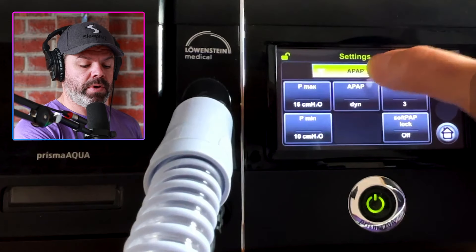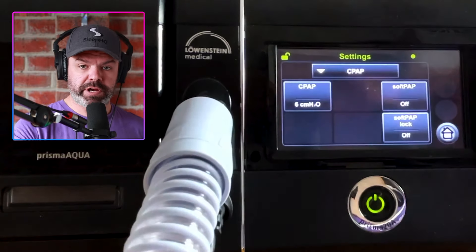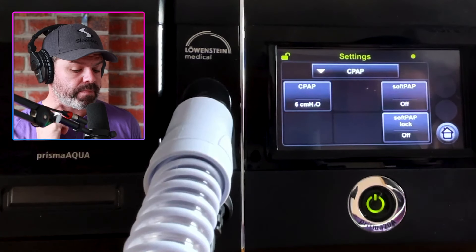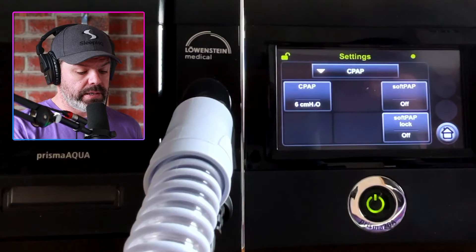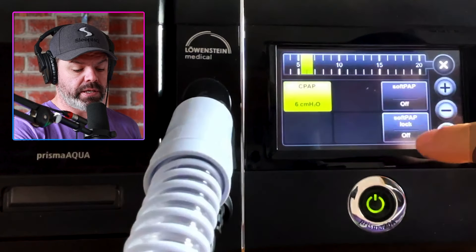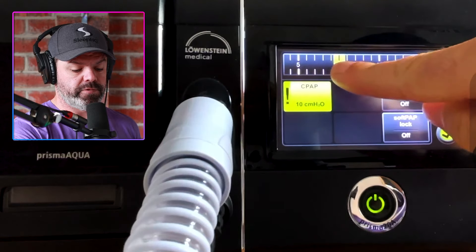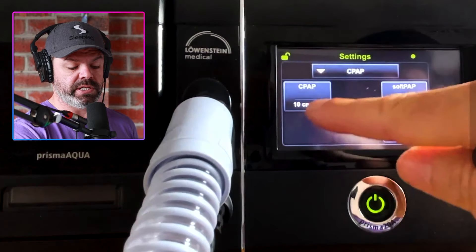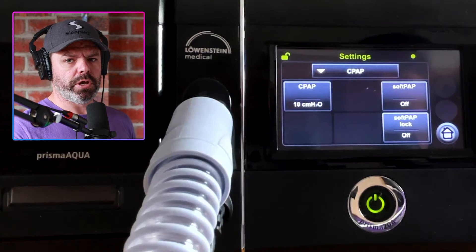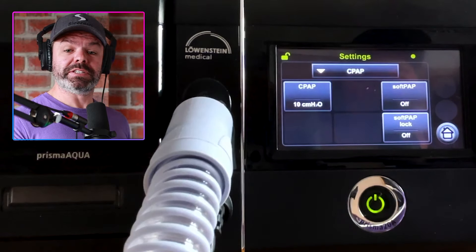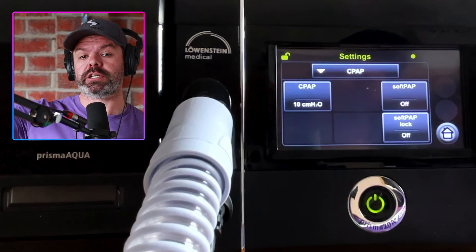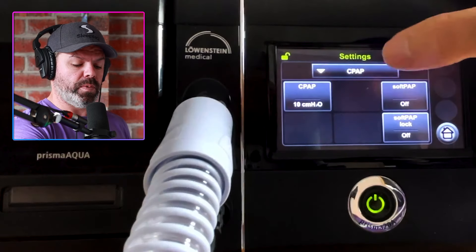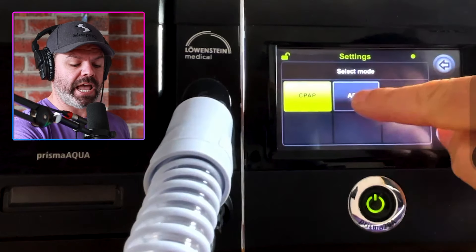Let's go to CPAP mode — changing now to fixed pressure delivery where the machine will deliver one set pressure. We can change that by clicking and dragging across then clicking the plus. I changed it from six to 10 centimeters because I had a lot of obstructive events and a high AHI, so I needed an increase in pressure. Once again we can change Soft Pap, and we can get back to APAP mode from here.